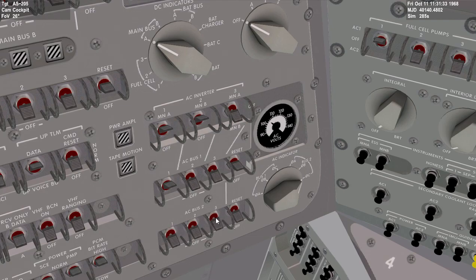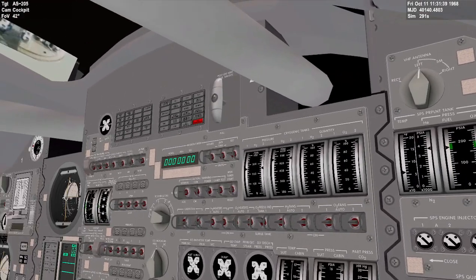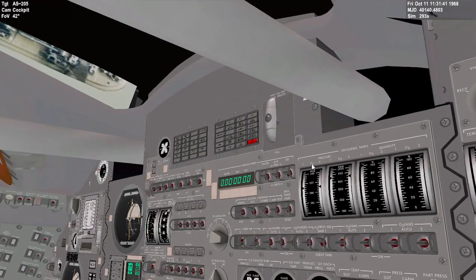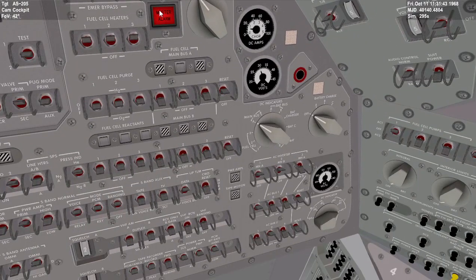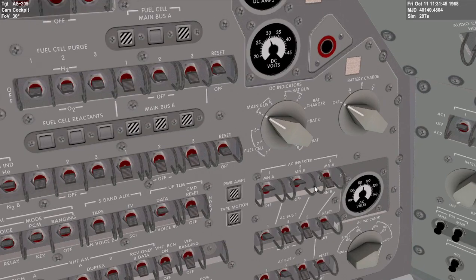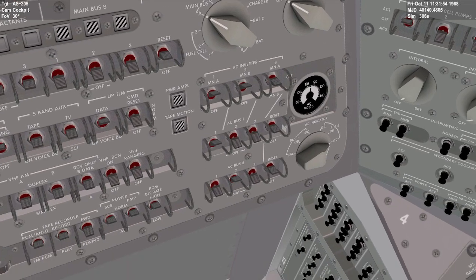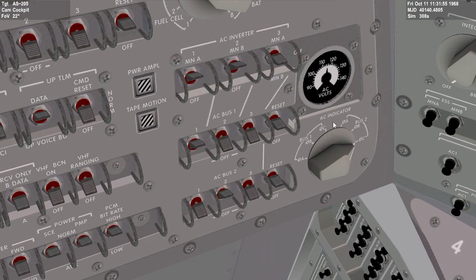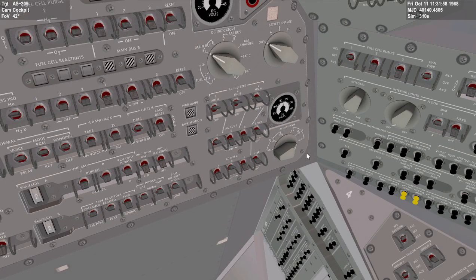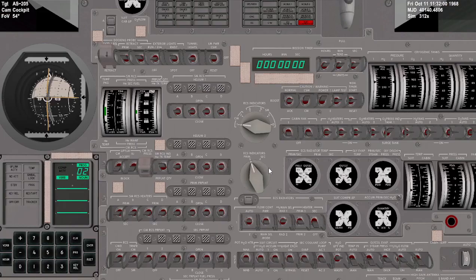Untie inverter 3. Tie inverter 2. Reset the sensing equipment. We get the master alarm. Light's not on though because we do have stable voltage. And unpower inverter 3. Verify stable voltage on all phases for all buses. So each bus has 3 phases, 3-phase AC current. And now back to acknowledge.